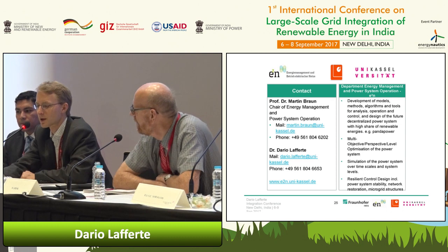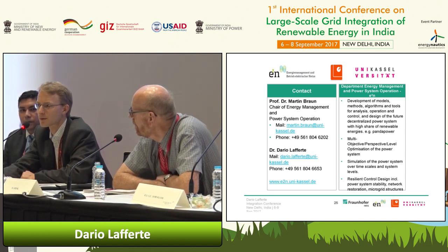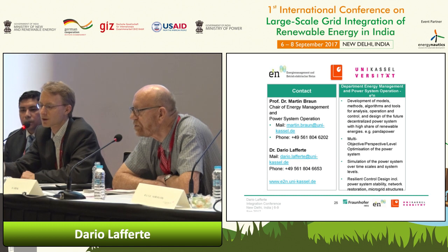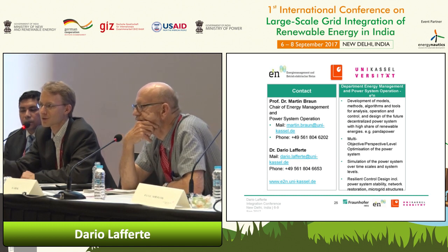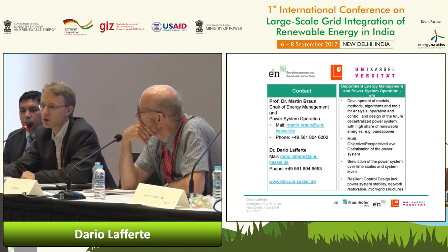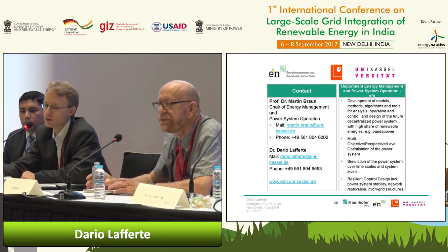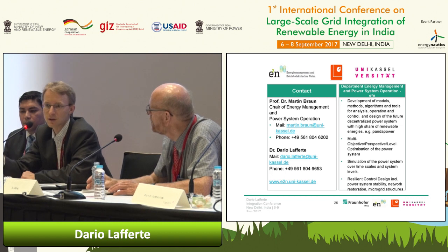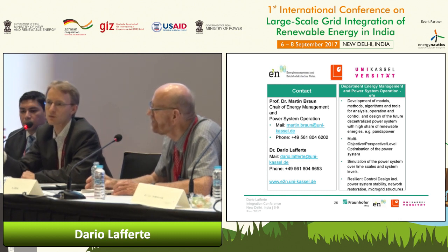That's a good question, actually. And as you already pointed out, this depends on the system size we are looking at. As I said, the national project Netzkraft is quite a large one, so we cannot present everything here, of course. So we have another case study, with a distribution system operator of a larger city, going into the high voltage system using gas turbines as grid forming units at the high voltage level, and so it's possible to resupply approximately 2/3 of the city. They have a synchronization device, and the idea is not to disconnect the city again and then re-energize by transmission, but to synchronize the existing island.